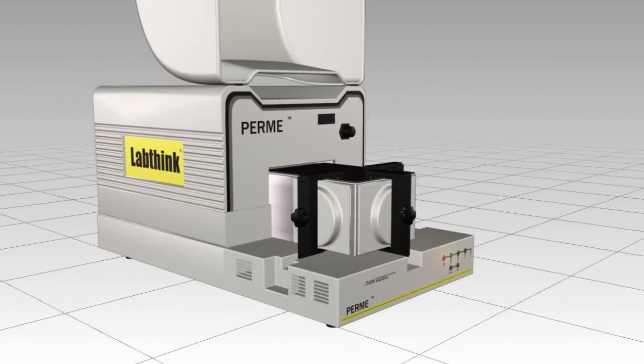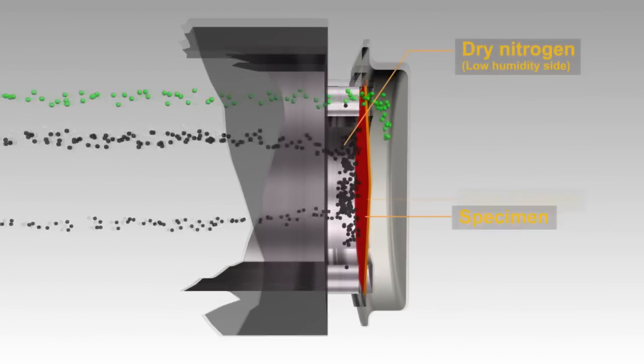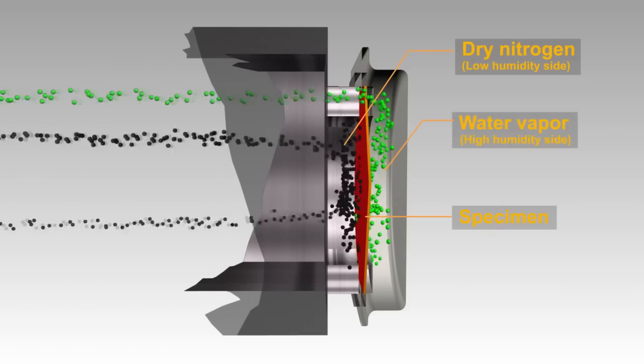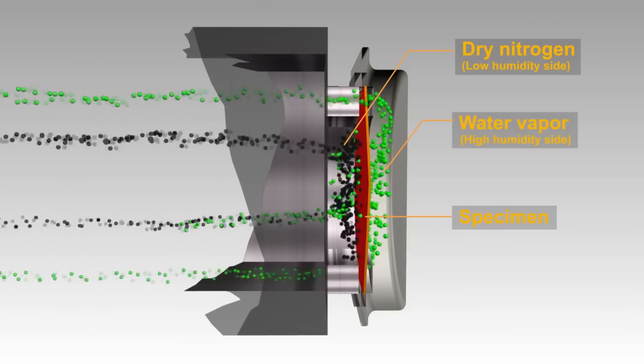W3330 works by firstly establishing a humidity difference across the two sides of the testing specimen. Then the water vapor molecules pass through the specimen from the high humidity side to the low humidity side.